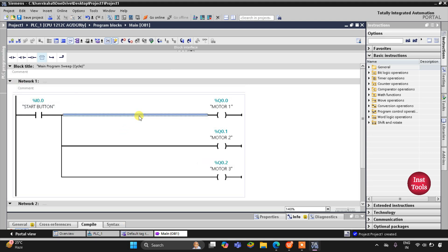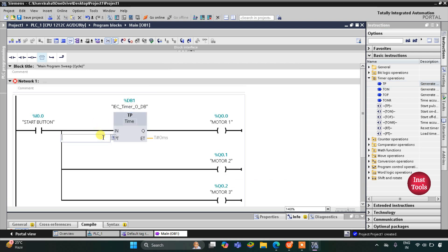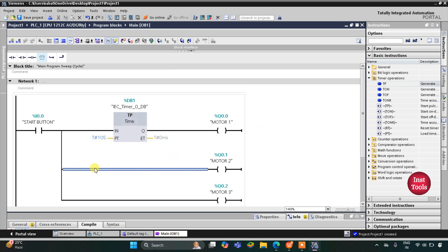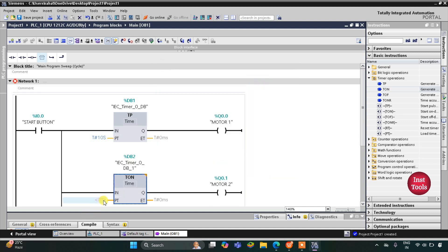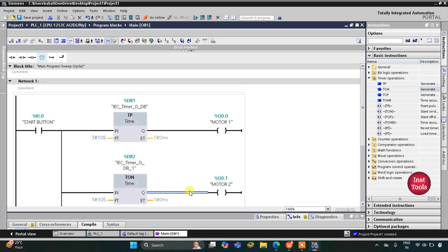Motor 1 should remain on for 10 seconds only. For that I'll go to Timer Operations, double click on TP (pulse timer), and click OK. The preset value will be 10 seconds so Motor 1 turns on for 10 seconds and then turns off. For Motor 2 to turn on after Motor 1 stops, I'll insert a TON (on-delay timer) with a preset value of 10 seconds.